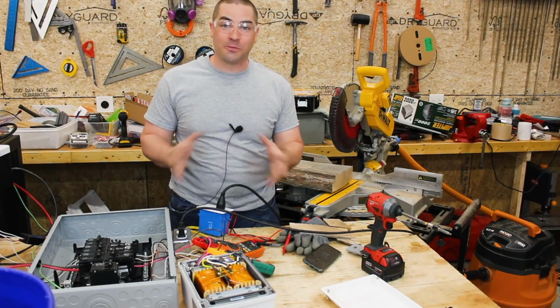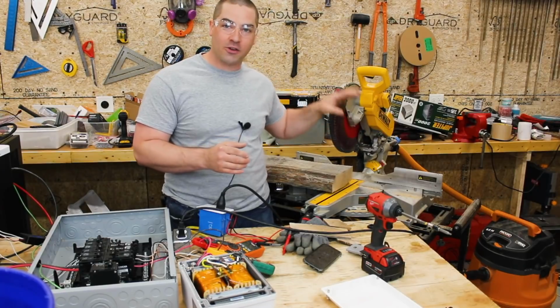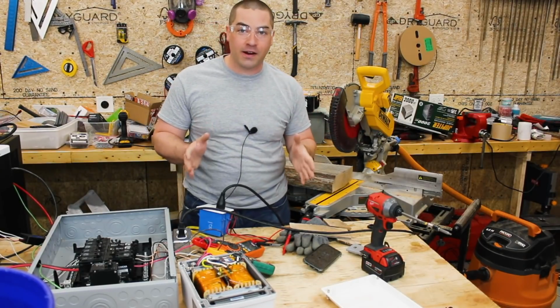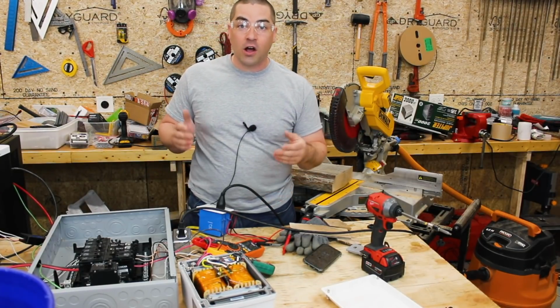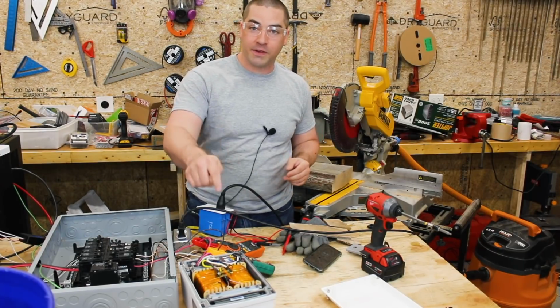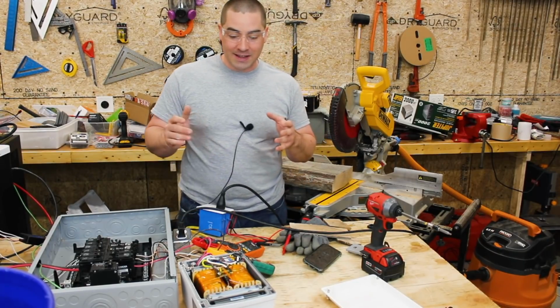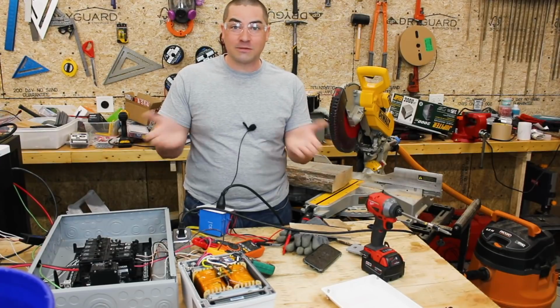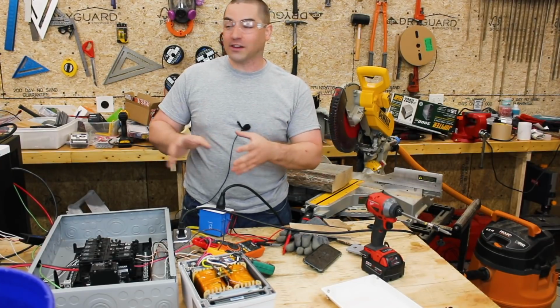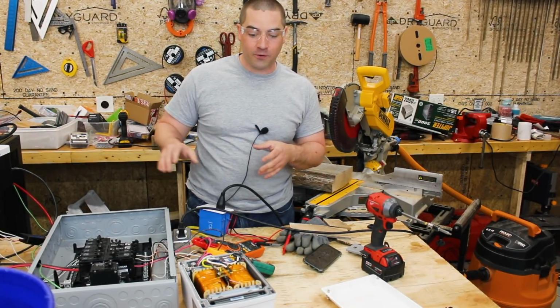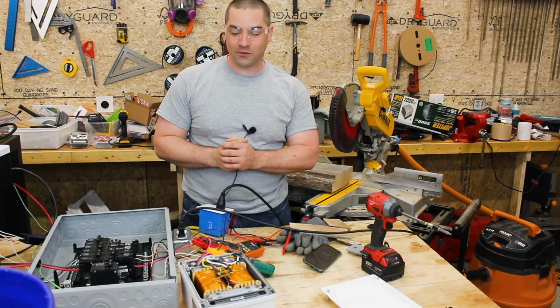I find that super exciting, that when the wet dry vacuum and the miter saw are both running, but they're on different phases, almost no amps are moving through the auto transformer. It's balanced out the 2 phases between each other, and all of that load is just going off on the 240 volt side. None is going through the auto transformer.